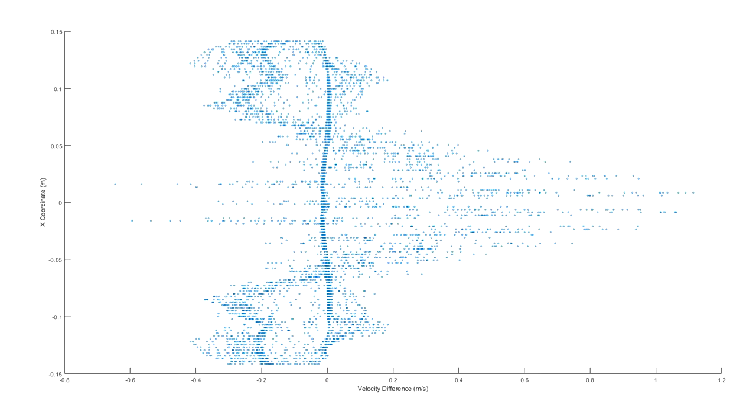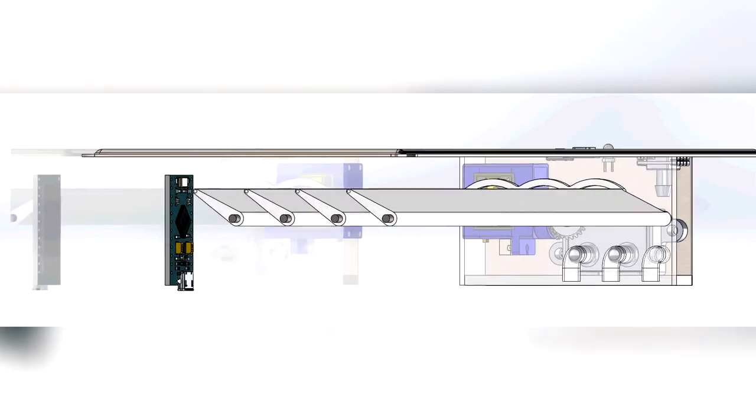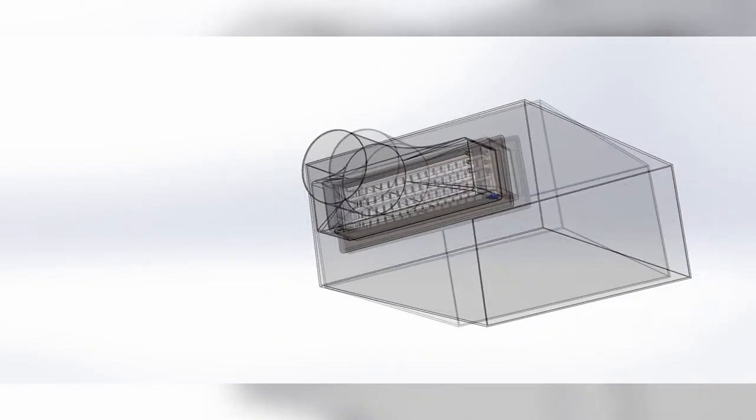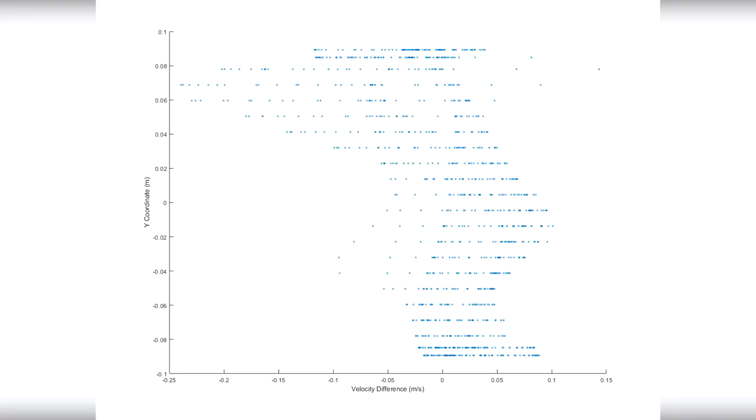Taking each node's surface area, then multiplying it by the velocity showed a negligible amount of airflow loss due to the electronics. Another simulation was conducted to determine if the air throw was also similar. Air throw is the velocity measurement of how well the air shifts from the vent to the rest of the area it is heating or cooling.